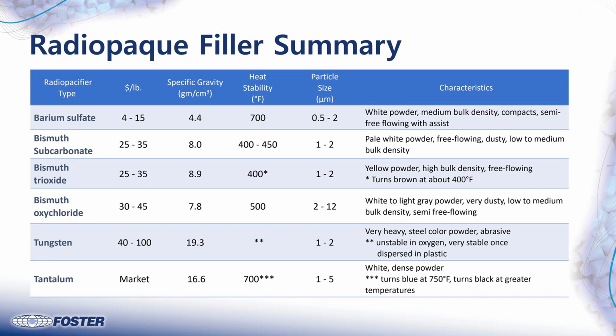Bismuth trioxide, you see this in more of the older legacy formulations. You would see this more in the fluoropolymers. And the reason being, bismuth trioxide, even though the density, specific gravity, is similar to any of the bismuths, the bulk density is very heavy, meaning when you're trying to manufacture a product, putting 30, 40, even 60% by weight of bismuth into a polymer, you have to feed all this powder into an extruder. So having a high bulk density helps feed the bismuth trioxide.